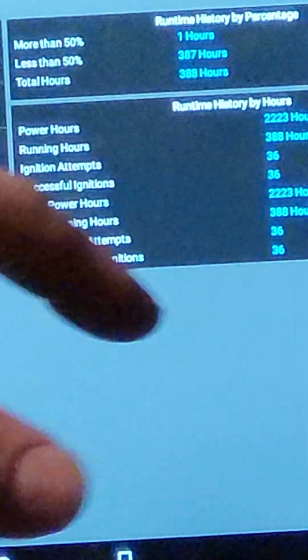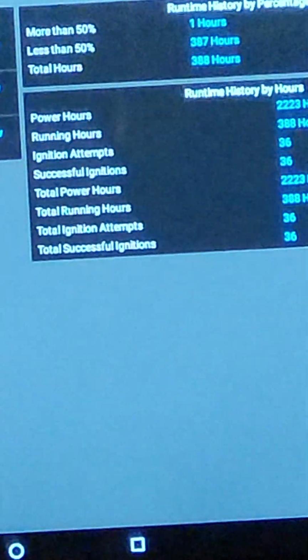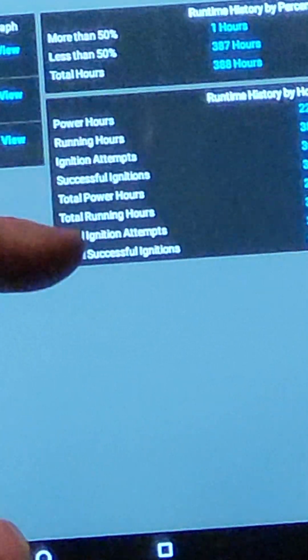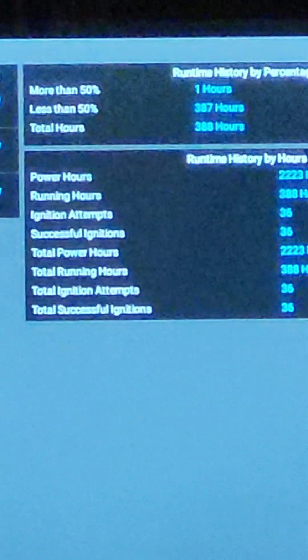You're staying caught up. Next, down below that is power hours, how many hours this boiler's had power to it. Running hours, 388. Ignition attempts, and then successful ignitions. So you have right now 36 ignition attempts and 36 successful ignitions. You haven't had a failure yet. That's good. Total running hours, total ignition attempts, total successful ignition attempts.